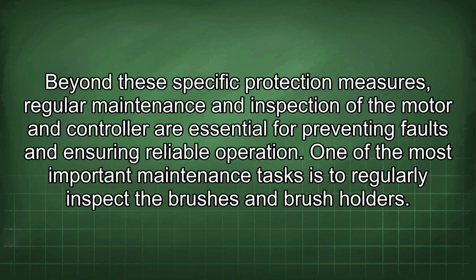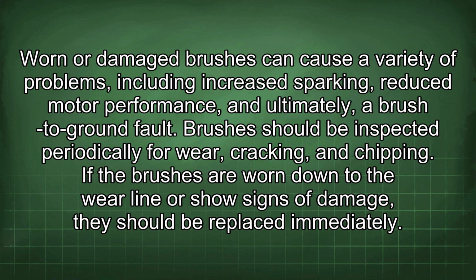ensuring reliable operation. One of the most important maintenance tasks is to regularly inspect the brushes and brush holders. Worn or damaged brushes can cause a variety of problems, including increased sparking, reduced motor performance, and ultimately, a brush-to-ground fault. Brushes should be inspected periodically for wear, cracking, and chipping. If the brushes are worn down to the wear line or show signs of damage, they should be replaced immediately.